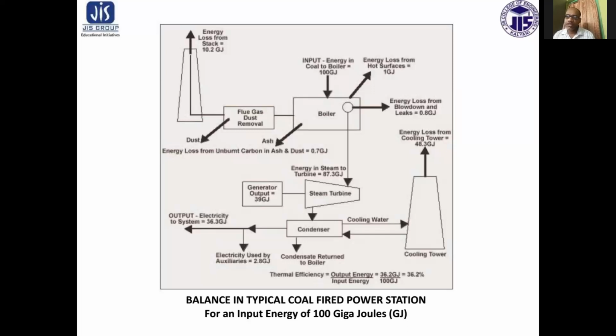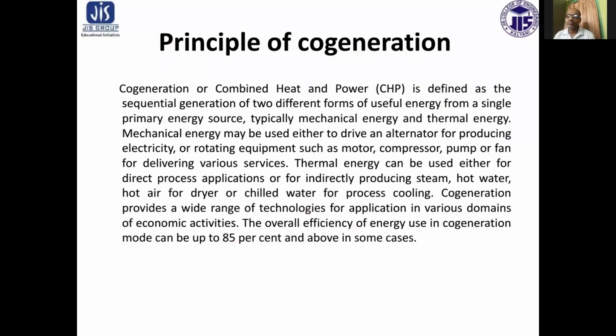So in a conventional power plant, the thermal efficiency ultimately available as electricity is 36.2%, for an input energy of 100 gigajoule. The major losses in a typical coal-fired power station are in the condenser and cooling tower, where nearly half the energy is lost. Another major source of loss is the flue gas. So now we understand why we need cogeneration, because the majority of the energy is lost in a conventional power plant, and only 35 to 36% of the energy is converted into high-grade energy.